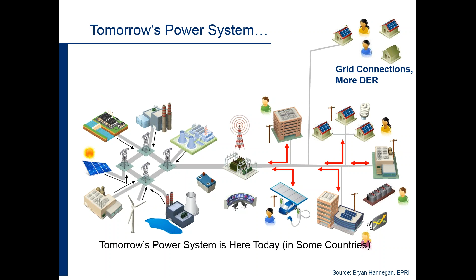The concern that we hear most often from utilities is that of voltage control. We also hear concerns related to reverse power flow, protection system coordination, as when you start pushing current in different directions, fuses and circuit breakers might not coordinate as they were designed to. But also we hear unintentional islanding and power flow as additional concerns. Increased equipment operations to regulate voltage, for example, switching capacitor banks, can decrease lifespans of devices while also increasing maintenance needs.